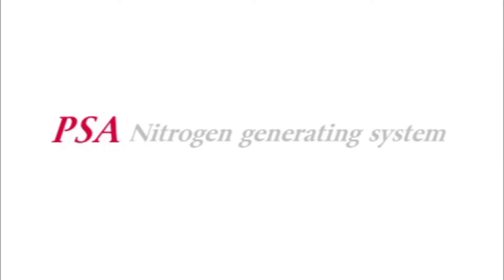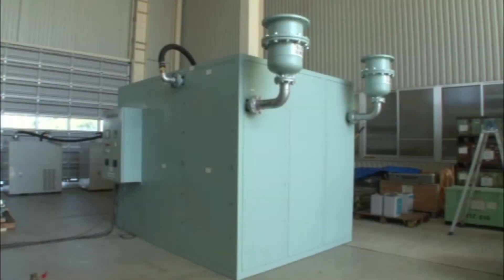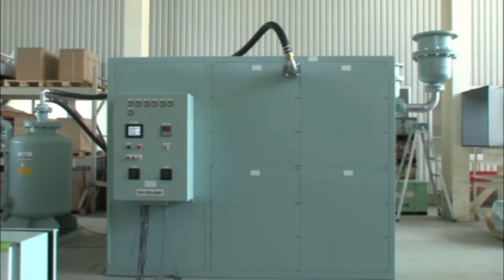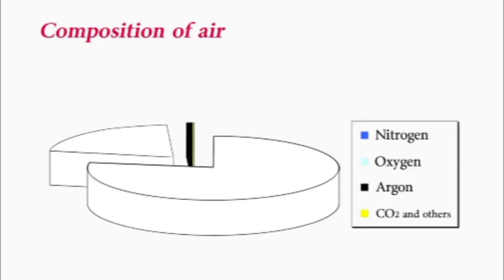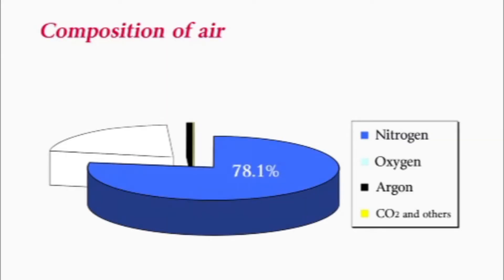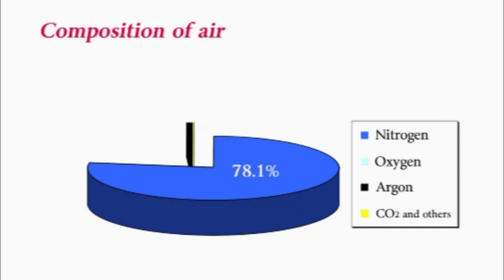Maekawa's Nitrogen Gas Generating System is based on PSA technology — Pressure Swing Adsorption. This system produces nitrogen gas from the air by utilizing special carbon molecular sieves. The composition of ordinary air is 78% nitrogen, 21% oxygen, and about 1% other gases such as carbon dioxide or argon. By removing the oxygen from this air, nitrogen gas is produced.